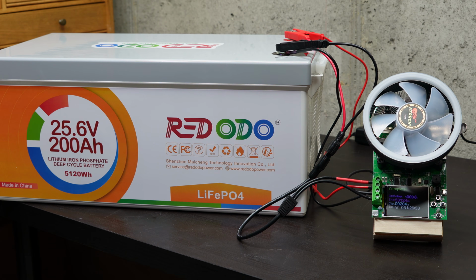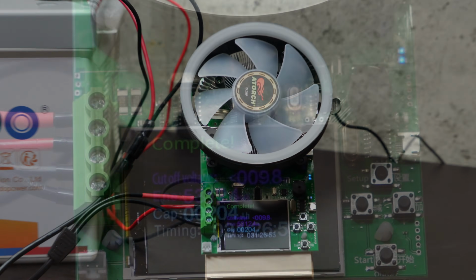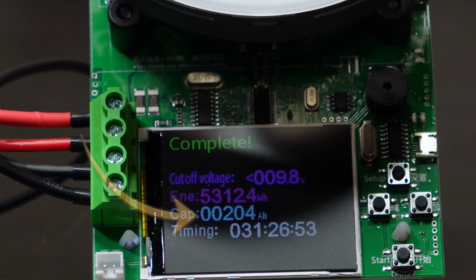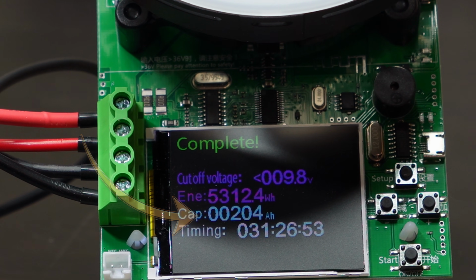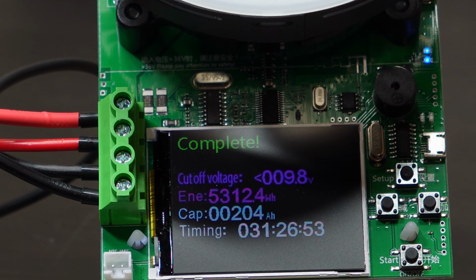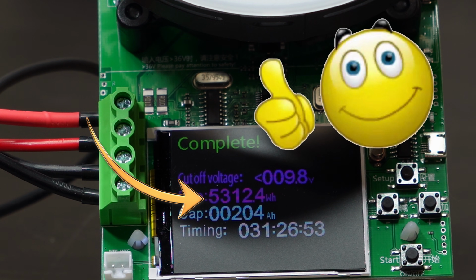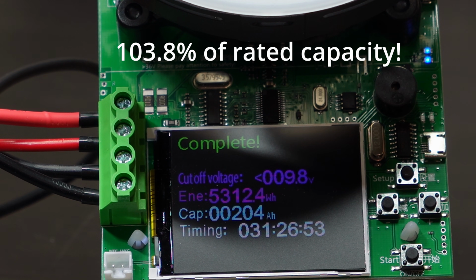30 hours later — okay, looks like our test is done. Let's see what we actually got. Zooming in, second from the bottom, we got 204 amp hours, and the total running time for this test was 31.5 hours. From a watt hour standpoint, we got 5,312.4 watt hours — a pretty significant bonus over the 5,120 watt hour rating of this battery.